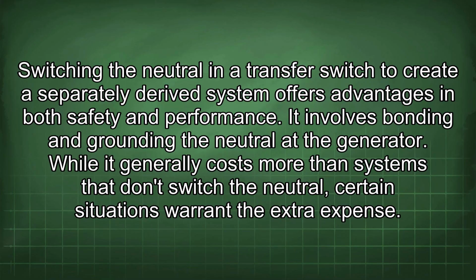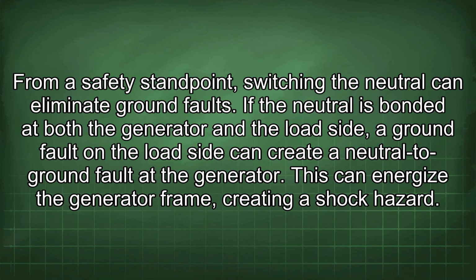Switching the neutral in a transfer switch to create a separately derived system offers advantages in both safety and performance. It involves bonding and grounding the neutral at the generator. While it generally costs more than systems that don't switch the neutral, certain situations warrant the extra expense. From a safety standpoint, switching the neutral can eliminate ground faults.